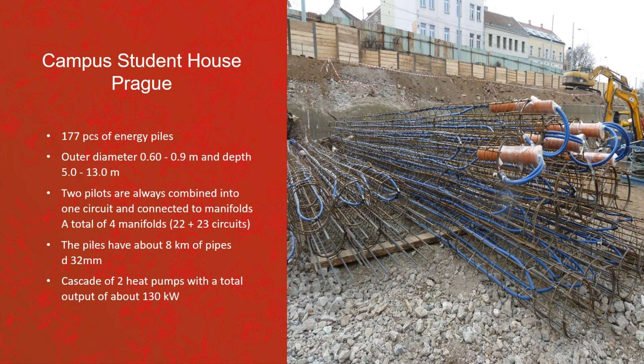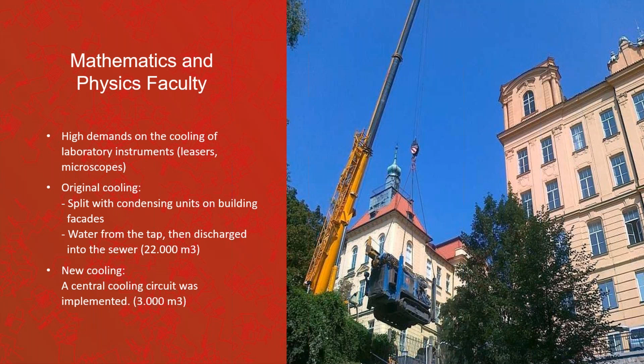The last project is Mathematics and Physics faculty. The operation of the school has high demands of the cooling of laboratory instruments, lasers, microscopes, etc. The original method of cooling was using the split units with condensing units on the facades of buildings, and the cooling medium was tap water, which was then discharged into the sewer. General 22,000 cubic meter. A central cooling circuit was implemented as a new method of cooling, now only 3,000 cubic meters.